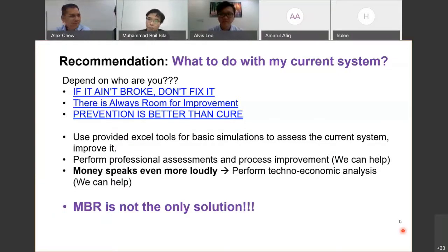So when you have this kind of problem, it's time for you to shift from normal activated sludge to MBR, because fixing this problem in activated sludge is a headache. I've been doing some projects to upgrade activated sludge, and we have sludge floating, sludge bulking. It's a nightmare. So if you have that problem, I will recommend, not because I'm a practitioner of MBR but because I want to help, the best way is to go for MBR.